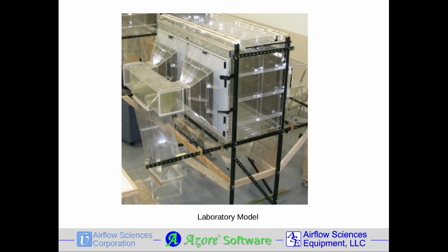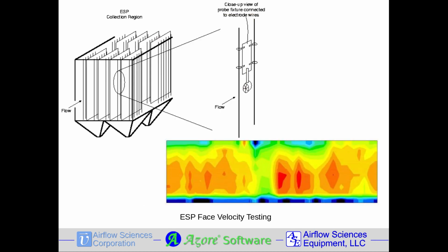The end result of the process is usually the design of flow control devices such as perforated plates, vanes, and baffles that can optimize performance and avoid costly problems. Both physical and computational fluid dynamic modeling are tools used in the analysis and optimization process. These methods can be used independently or in some cases together.